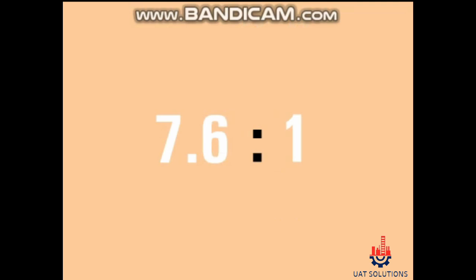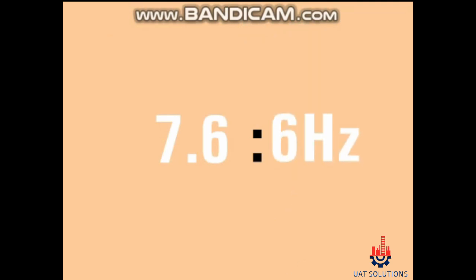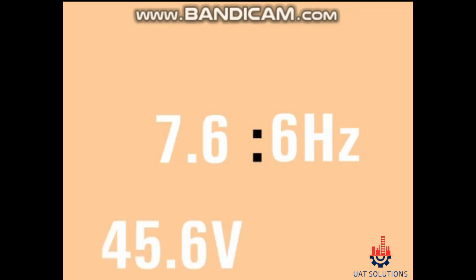As an example, to achieve 10 percent speed, a frequency of 6 hertz must be supplied. To properly apply electric power at 6 hertz, the output voltage must be 45.6 volts AC.